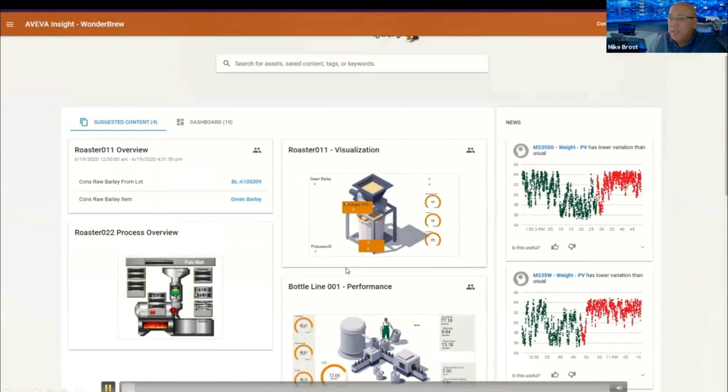News feeds can also now be multivariate. It will take basically every tag value that we send to the historian and compare it to every other tag value and find binary systems amongst all those tags. It automatically does that, and then it will report to us when those binary systems no longer track each other. For instance, you may have temperature and pressure in a boiler. Well, if they don't track, then there's something wrong with what's going on.